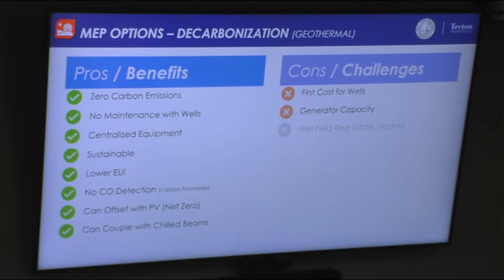So really, the cons: the first one is the cost of wells. Your well field is your biggest cost in this. Your generator is also a capacity issue as far as heating, you have to deal with the electrical production. But what we do in those cases is we don't size the generator for full protection, we size it just for a portion, and we rotate around the building to maintain it so you don't have a freezing condition, so you don't have to pull full backup for that. Do you have a larger service for the building or no? No, because your air conditioning is electric anyway, it's the same service size. It doesn't grow, that's a benefit. There's no growth in electrical from that point of view, you're just using electricity to heat in the winter.